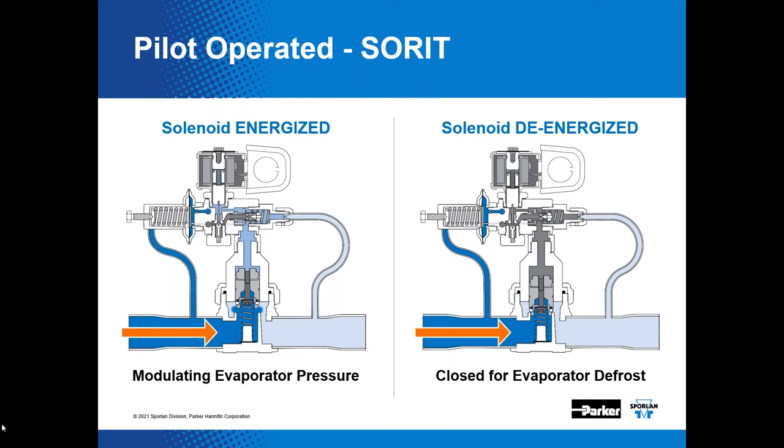To defrost the evaporator, the solenoid component is de-energized, allowing discharge gas to dump on top of the piston and provide a positive closing action. In that case, you don't get the bleed and the piston is forced closed, shutting the valve. The solenoid valve must be energized for the valve to modulate if it is a SORIT version.